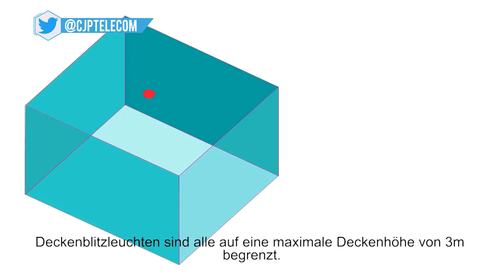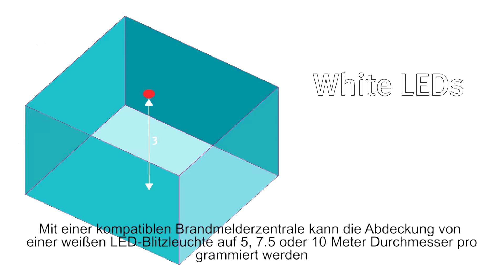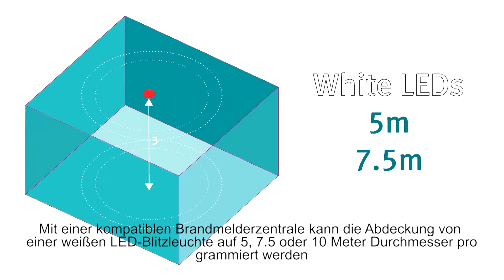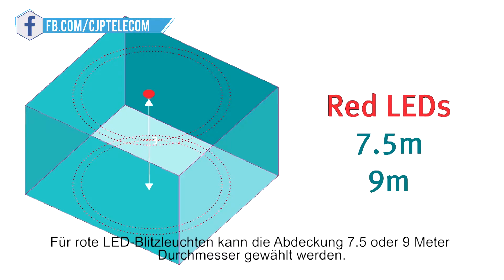Both devices have the capability of variable coverage volumes, which helps simplify the range. For the ceiling beacons, these volume coverages are all based on a maximum ceiling height of three meters, so subject to control panel compatibility, you can set the coverage of a white LED beacon to 5, 7.5 or 10 meters diameter. For red LED beacons this coverage could be set to 7.5 or 9 meters diameter.